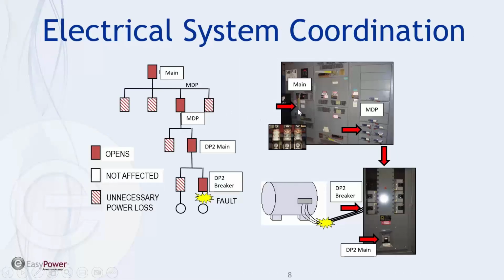So we have a main switch that feeds the main distribution panel, and the main distribution panel breaker feeds the main breaker on this particular panel. Then we have a breaker that feeds the motor. We want this breaker to open if we have a short circuit or a ground fault on the motor, which would just isolate the motor. But what happens in that time current curve that we talked about is the main distribution panel up here goes. So now all of these loads, each panel with everything fed from those panels, are de-energized.